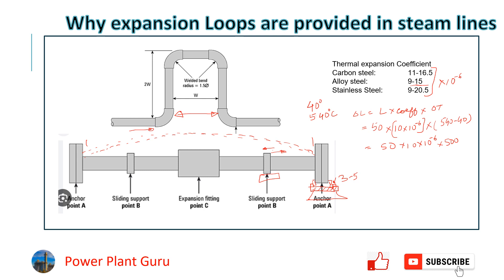There are sliding supports where the pipe rests and slides with some friction. The two end supports are the fixed anchor supports, and in between there is the U-loop to consume whatever expansion exists between those anchor points.